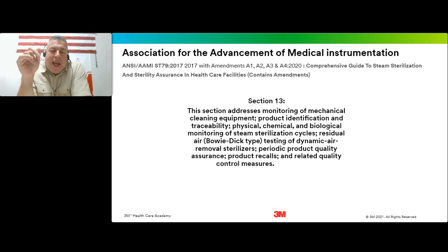Amendment A2 looks at inspection of insulated instruments. Very critical, very important update. Any insulated instrument that we're processing should be tested with an insulation tester. So that section addresses that.